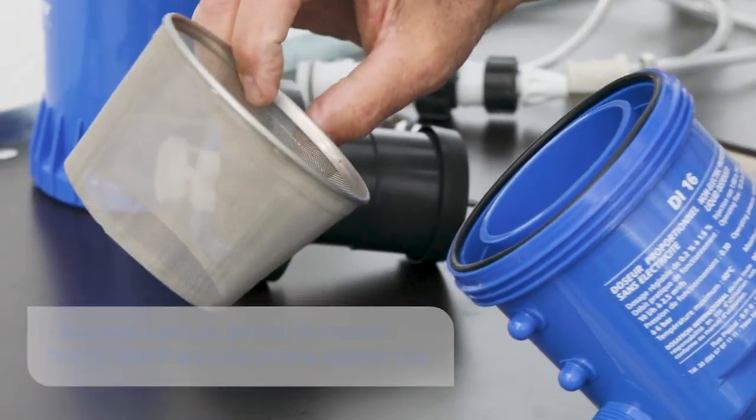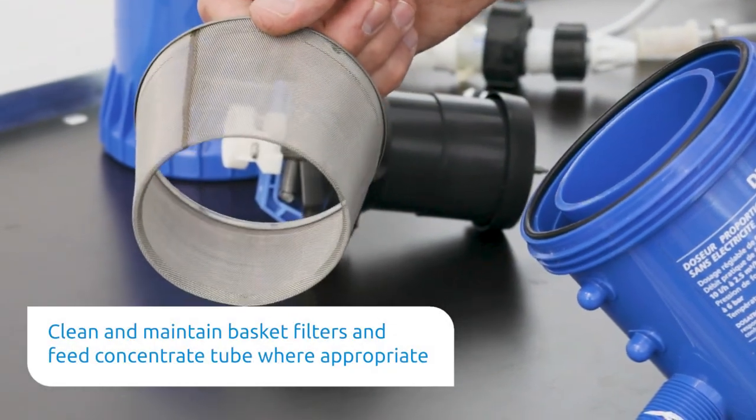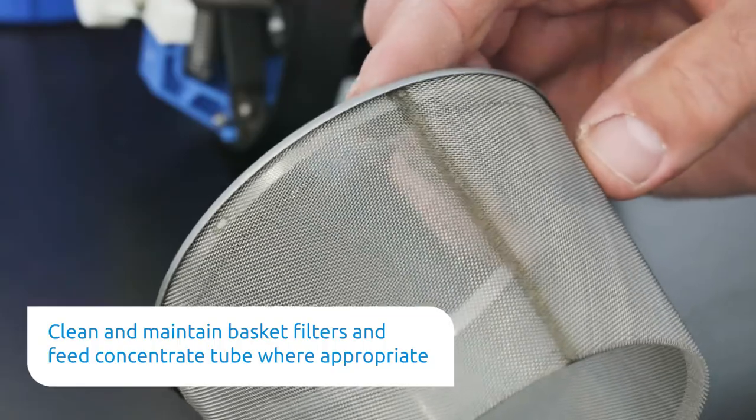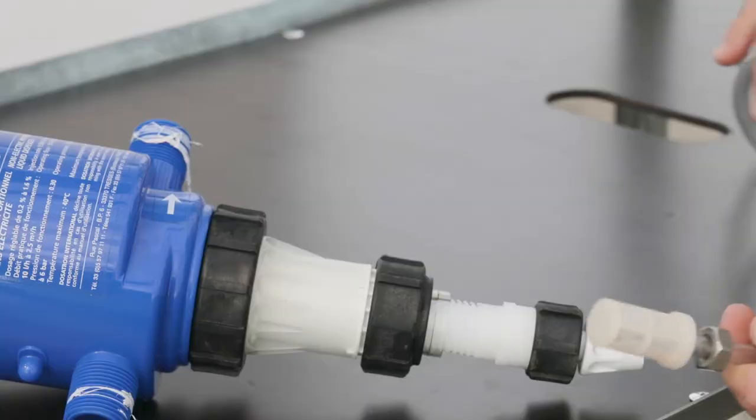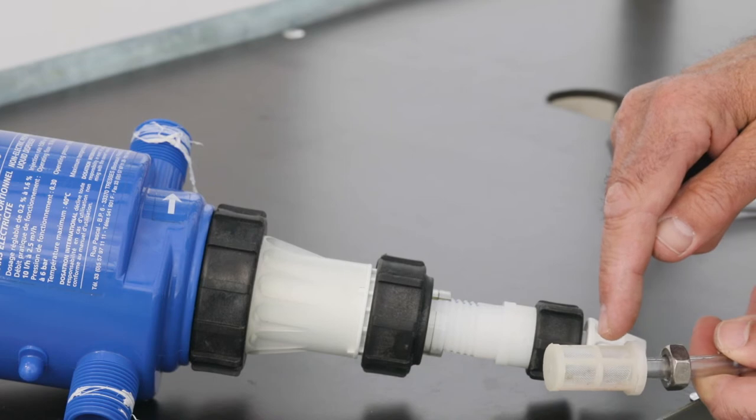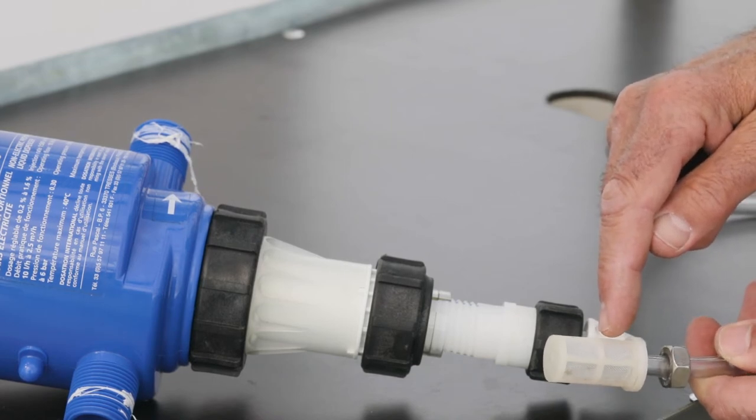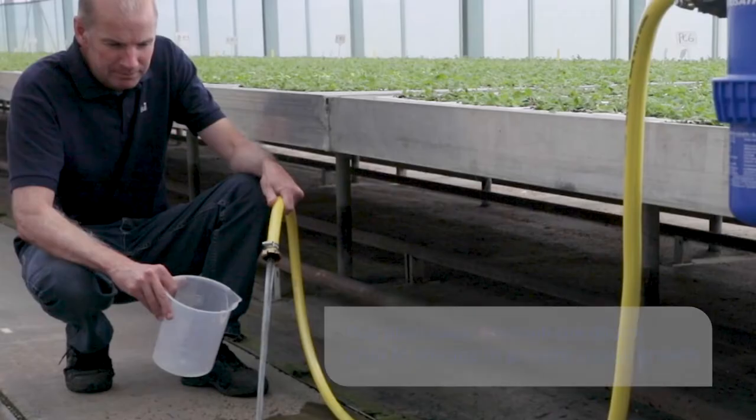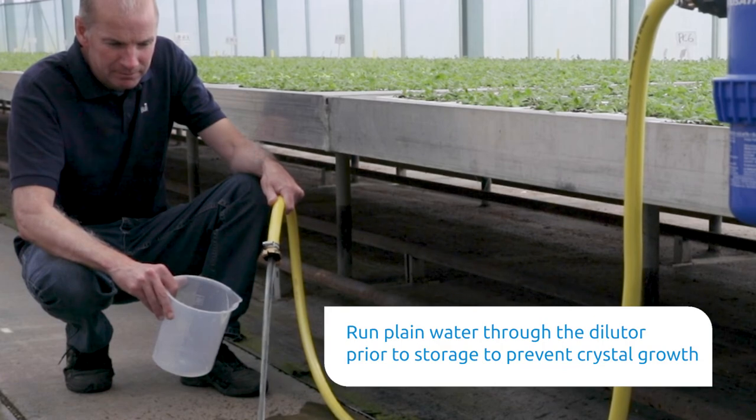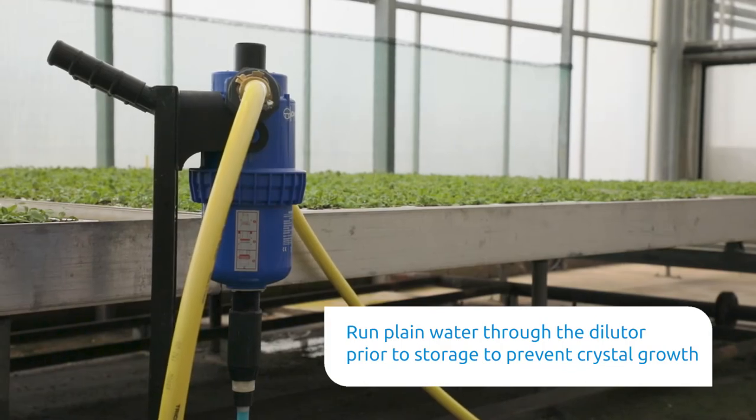Third point is to take the basket filters out and make sure they're clean and also make sure that the filter at the end of the feed concentrate tube is also cleaned regularly. The algae does tend to grow on these. Just run them through with plain water and prevent crystals forming in the actual piston area.